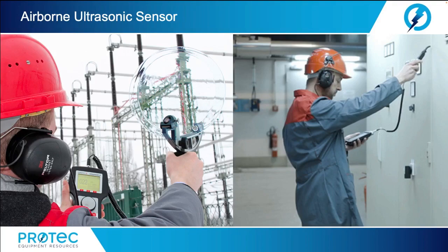All right, next let's talk about airborne ultrasonic sensors: airborne ultrasonic, parabolic dish concentrator, or ultrasonic extension wands. Each time a partial discharge event occurs, an ultrasonic emission is transmitted from the site of the defect. The emissions are typically in the ultrasonic range from 20 kilohertz out to around 300 kilohertz, and may also extend lower into the audible range. If an insulation defect is close to the surface, then the ultrasonic signal will spread out and become airborne. The airborne ultrasonic signal may be detected by one or more of the three types of airborne ultrasonic sensors which are commonly used. An extension wand can be used to listen in hard-to-reach seams of switchgear cabinets or other enclosures.